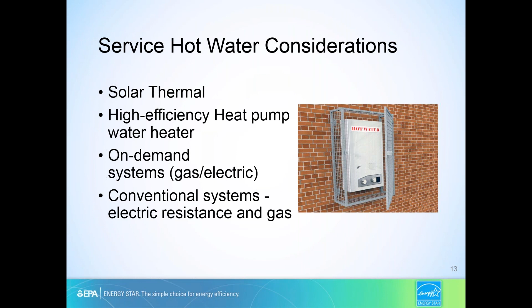Definitely look at gas if you have an on-demand system and you have gas service. Electric can be great too. However, you need a larger electric service, and you really got to take a look at your considerations if you need that on-demand electric service, because it's going to be a little bit more expensive. You're going to pay a little bit more for the kW. And I would really advise folks that if you don't need to make a change, or if you have a recent hot water heater that you're not looking to remove, go ahead and get one of those thermal blankets for it. Just making sure that it's drained annually or serviced properly, and you have a thermal blanket wrapping around it, it's going to get a little bit more performance, and it's not going to have that standby heat loss that you see with a hot water heater that just sits there for most of the day, radiating that heat out into the space.